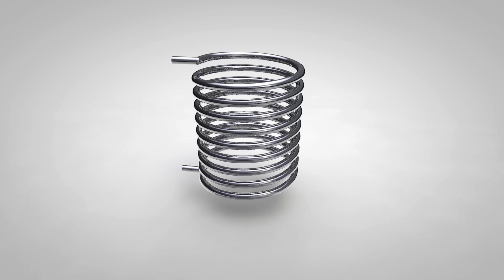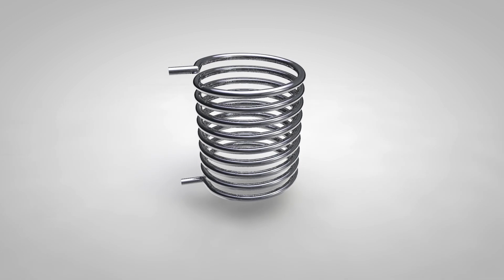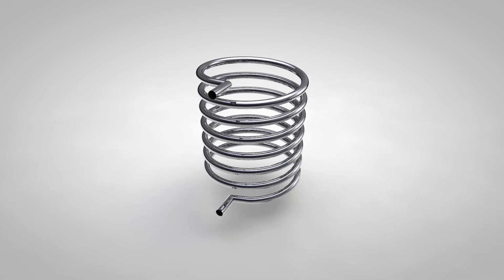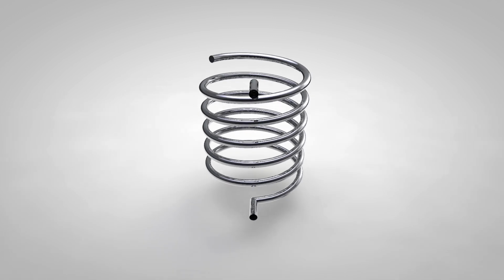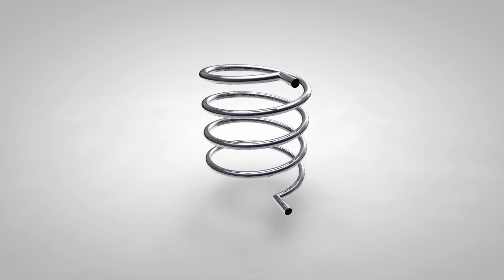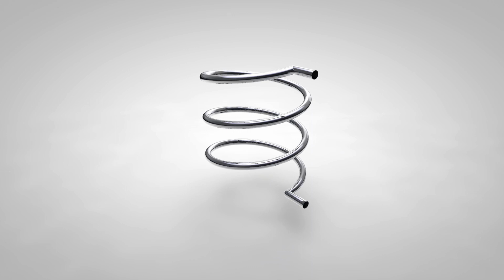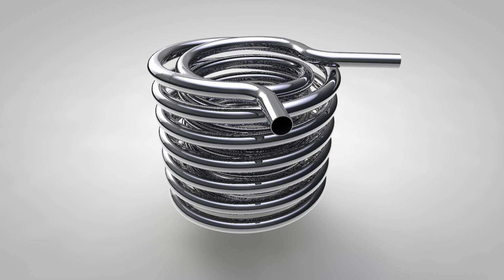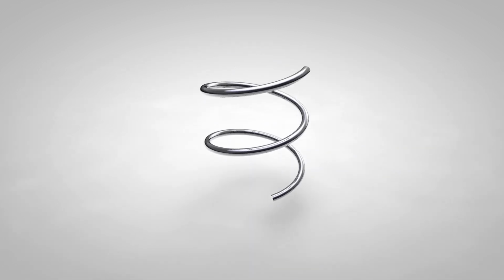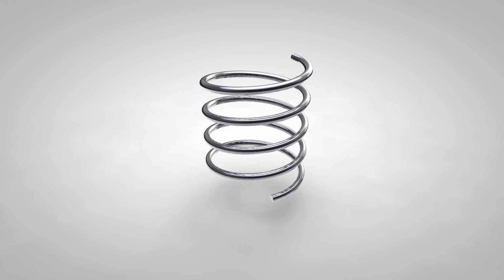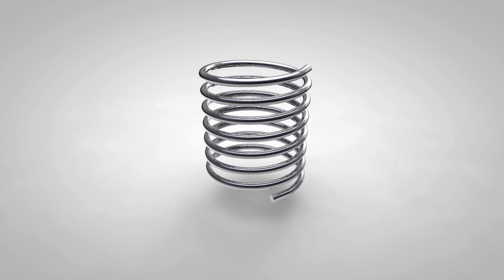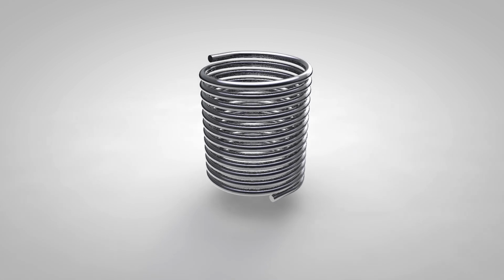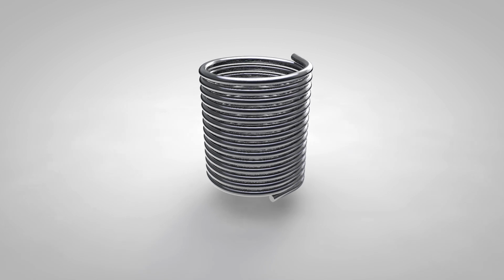Moving on now to the coil design factor, its pitch. The coil pitch determines the application a cylinder can be used on. Although less important now as modern systems use a circulating pump, old gravity feed systems require a coil with a higher pitch so gravity can pull the water through. Gravity feed systems also can't benefit from space-saving coil designs such as coil-in-coil. On a modern pumped system, an excessively long coil can be self-defeating if the pitch of the coil becomes too tight. It will interfere with the circulation of the water around the coil and can result in slower heat-up times.